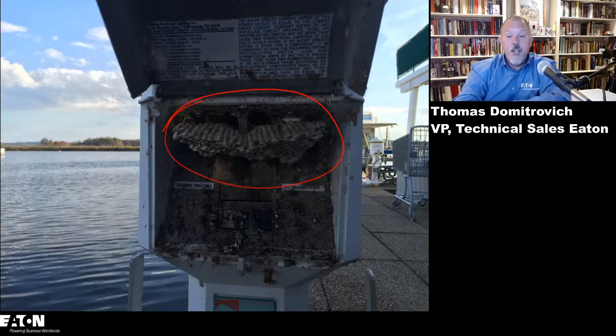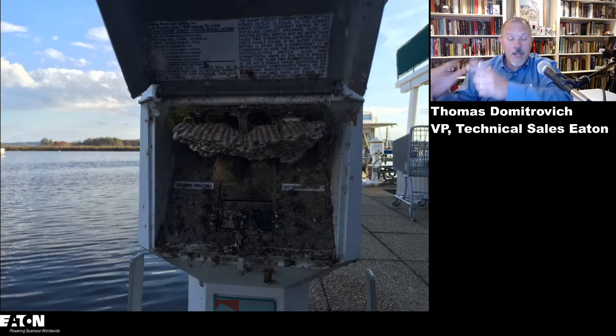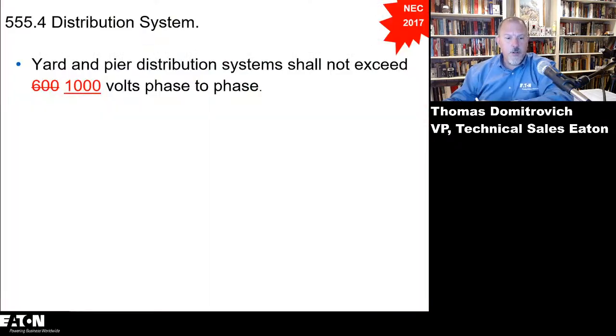In fact, we can't make these. These are created over time due to no or zero maintenance. You need to be performing maintenance on these things. If you're a contractor involved with marina type applications, get a contract together with your marina to go out there annually and inspect per NFPA 303 these pedestals and the infrastructure.